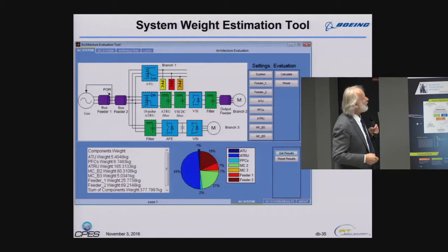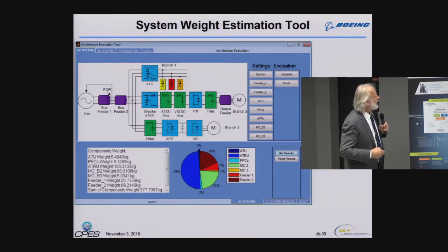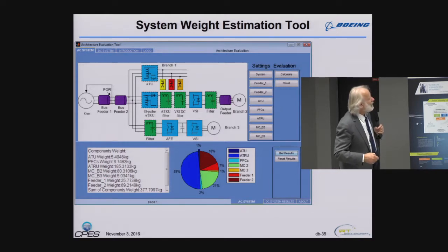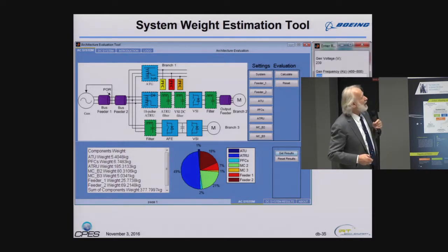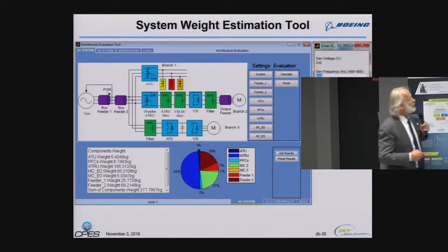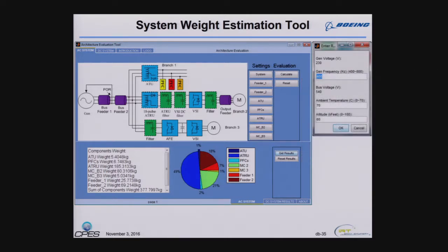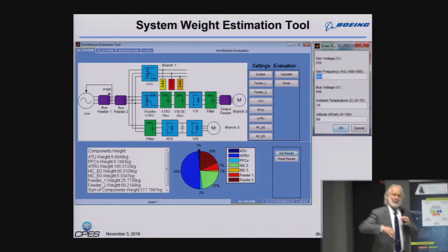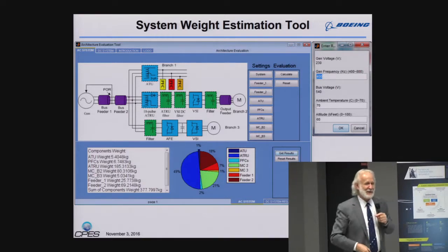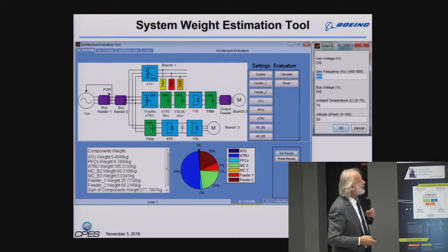For example, this one calculates the total weight of the system, from the generator all the way to the feeder to the motors. You can change specifications - what is your generator frequency, what DC bus voltage do you want, what altitude you want because of partial discharge and how much insulation, and so forth. It was all calculated in there.